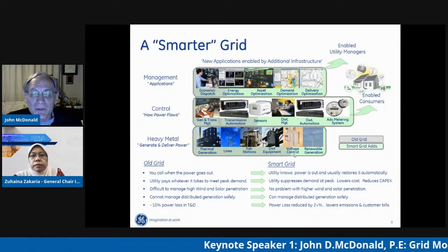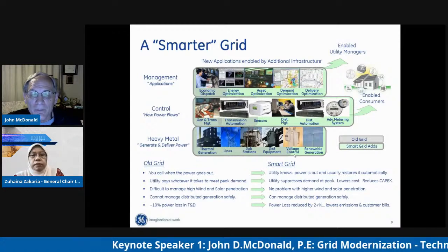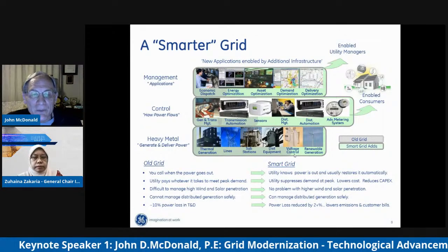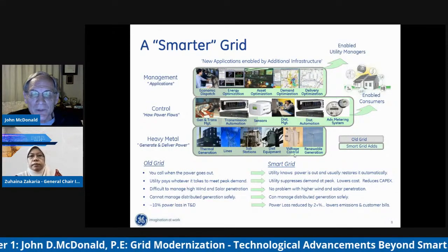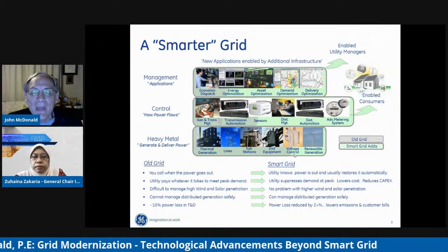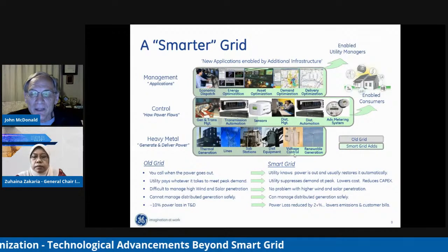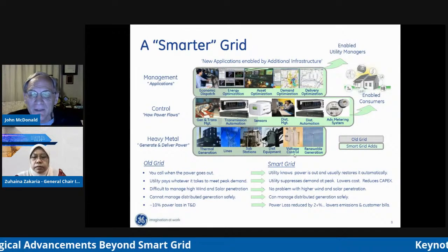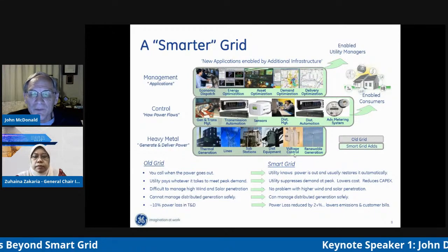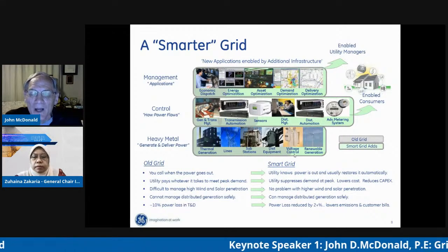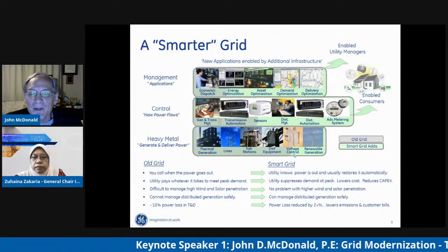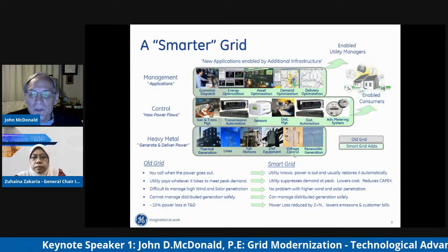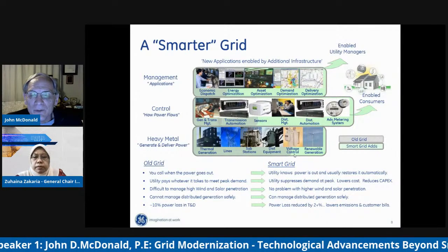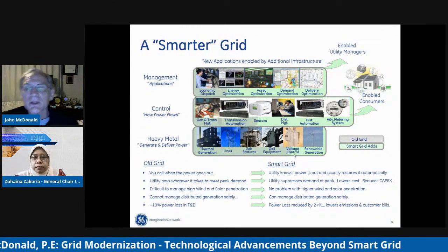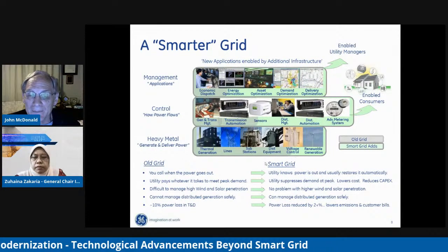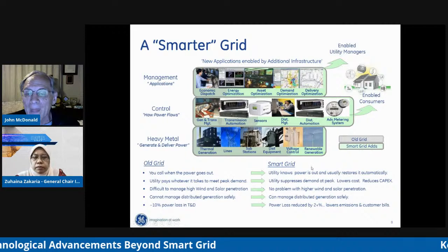There are significant benefits to both voltage control and VAR control. In the mid-1990s, I wrote a power factor control application for a SCADA vendor I was working for, and a utility in the northeast United States implemented it on their existing SCADA system, saving over $250,000 per year in losses. Today, for every dollar a utility invests in distribution optimization, they're getting $5 to $6 back—a very strong benefit-to-cost ratio.